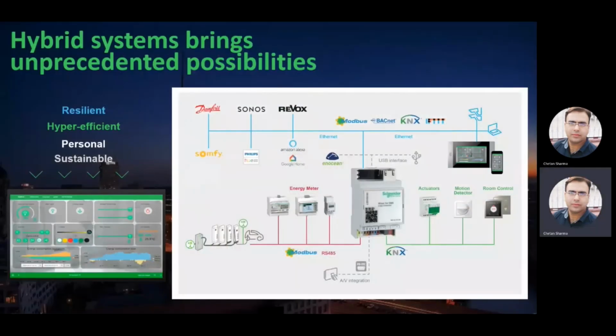Having a hybrid system brings infinite possibilities. So thanks to the Visor for KNX IoT controller, which is also called a multi-protocol gateway, probably one of the strongest gateways available for home automation right now, we can, in addition to our conventional KNX installation, also add our energy monitoring. We can also have third-party integrations on standard protocols like Modbus, BACnet, IFTTT, Ethernet, and many more.